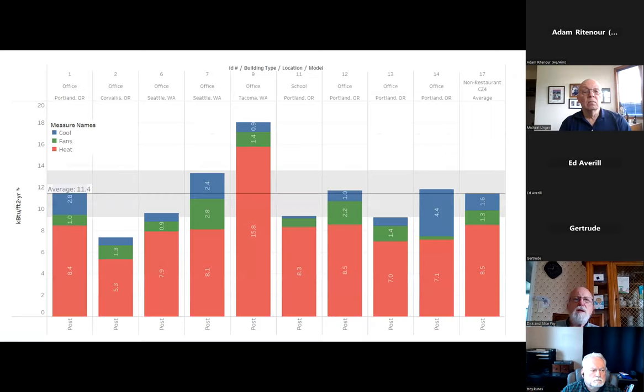Right, I think this is probably my favorite slide, because to me this says the most significant results as far as VHU DOAS conversion and what that might mean for energy savings. Despite the wide range of the whole building EUIs that we saw in the last slide before the conversion, which ranged between 26 and 122, if we excluded those restaurants and the cold climate projects, we actually see a consistent post-conversion HVAC EUI of about 11.4. And of the 9 projects that we show here, 7 of them were within 2 points of that 11.4 average.